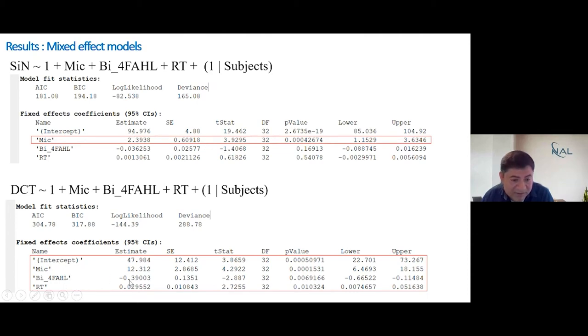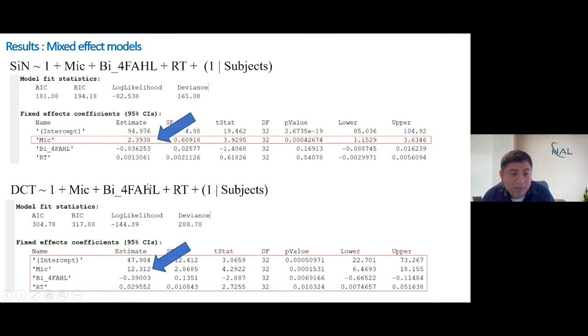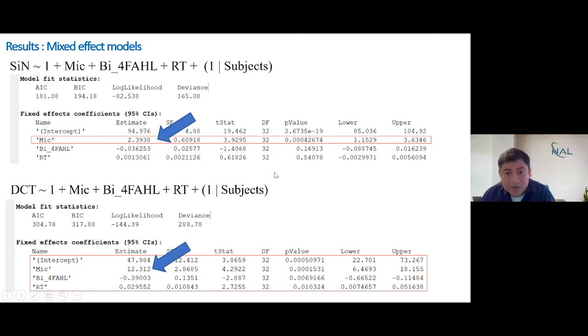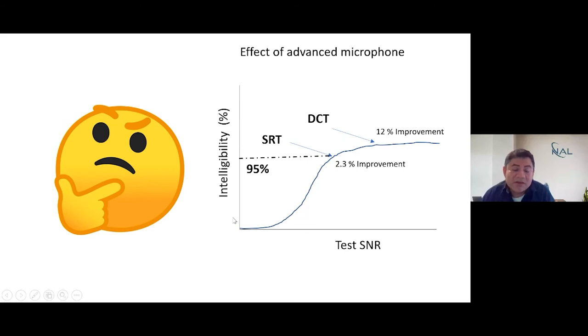The two models are significantly different from each other. The intelligibility model shows only an effect of the microphone, whereas the DCT model shows effects of a number of other things including reaction time — which is very interesting, though I won't focus on that today. What I am most interested in is the effect of the microphone: we see about a 2.3 percent improvement going from Pinna Omni to the more directional cardioid average, and about 12 percent improvement going from Pinna Omni to the beamformer — the more advanced processing strategy.